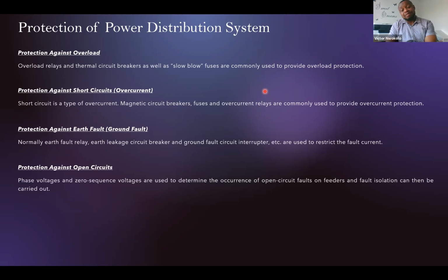because overload can easily damage some of your systems, especially cables, and can also eat up some components within your electrical system. So in order to avoid that, if overload is seen for a prolonged period, the protection device will cut it. The common types of protection equipment we use for overload are overload relays and thermal circuit breakers. The thermal circuit breaker senses the heat rise from the flow of current and trips. Some slow-blow fuses are used as well, because they monitor the slow rise in current for a period, then they react.